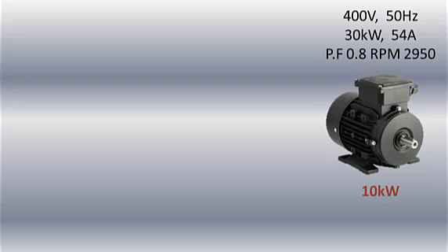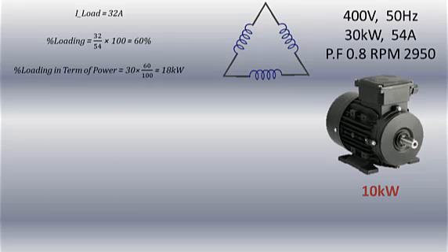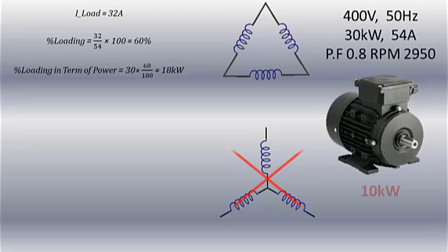For example, if the motor is running in delta connection and drawing 32 ampere, you can calculate its loading percentage relative to its nameplate rating. Since 32 ampere is 60 percent of its rated current, the motor is operating at 60 percent of its rated power, which is 18 kilowatt. Since this is greater than 10 kilowatt, the motor cannot be safely run in star configuration at this load.